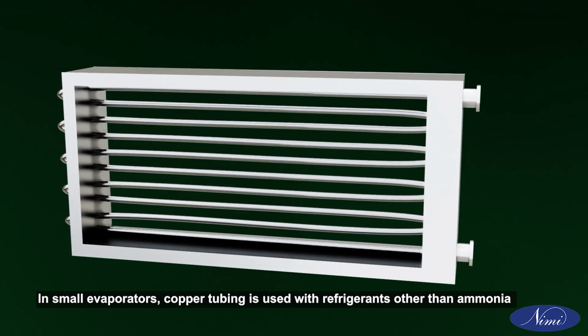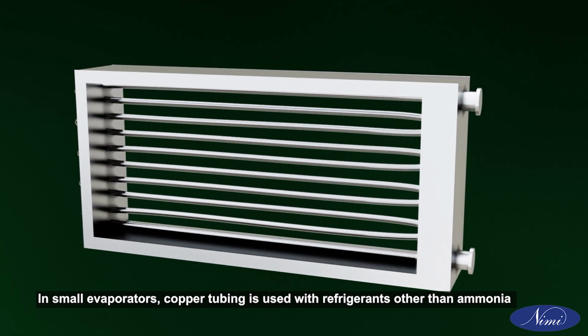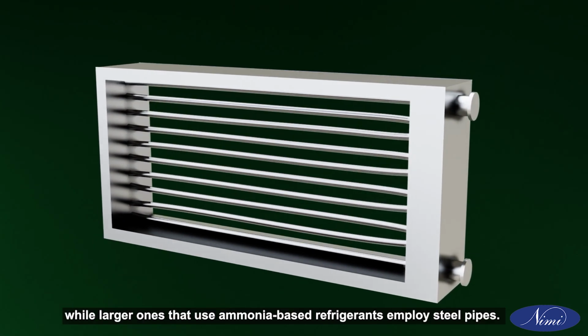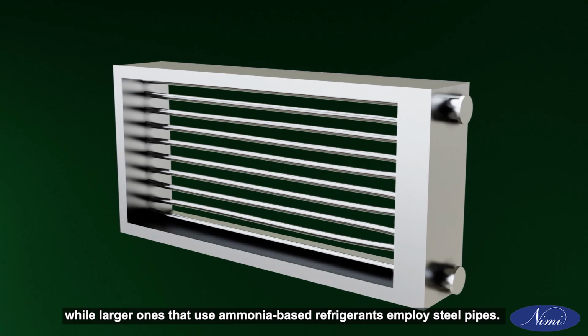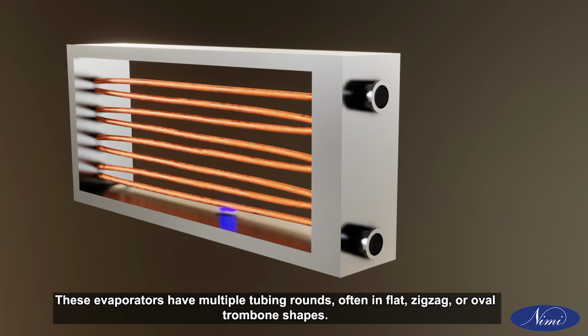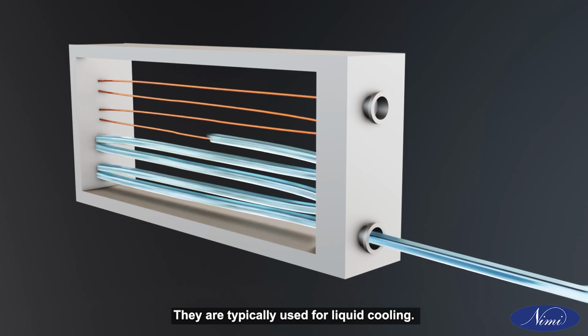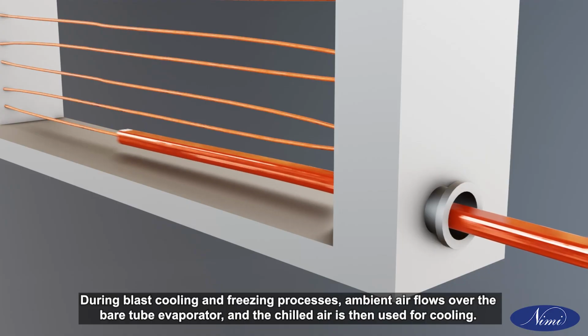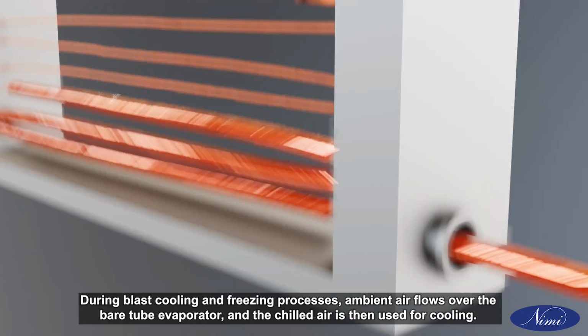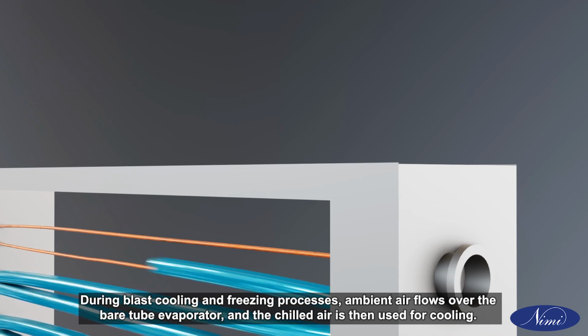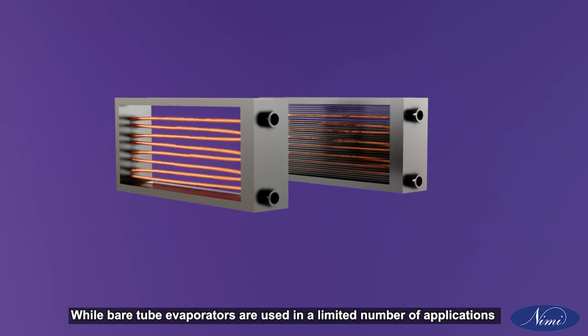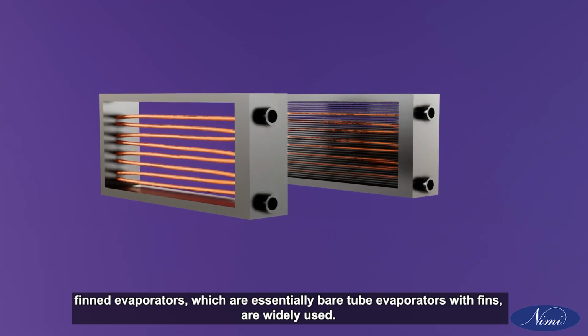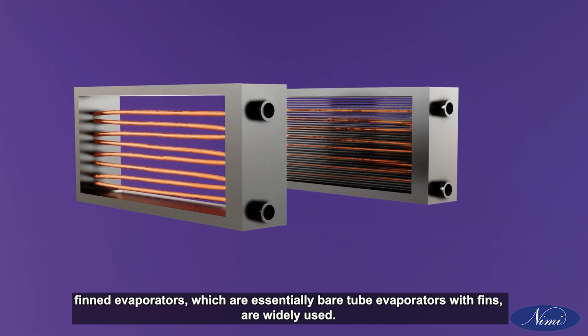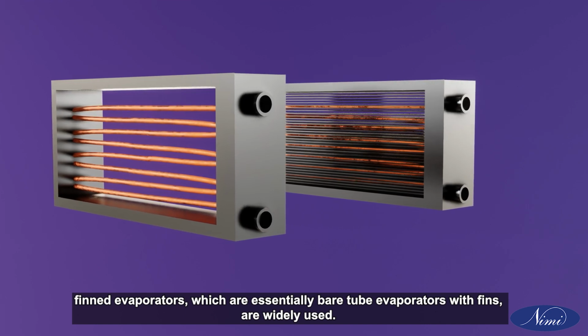In small evaporators, copper tubing is used with refrigerants other than ammonia, while larger ones that use ammonia-based refrigerants employ steel pipes. These evaporators have multiple tubing rounds, often in flat, zigzag or oval trombone shapes. They are typically used for liquid cooling. During blast cooling and freezing processes, ambient air flows over the bare tube evaporator, and the chilled air is then used for cooling. While bare tube evaporators are used in a limited number of applications, finned evaporators, which are essentially bare tube evaporators with fins, are widely used.